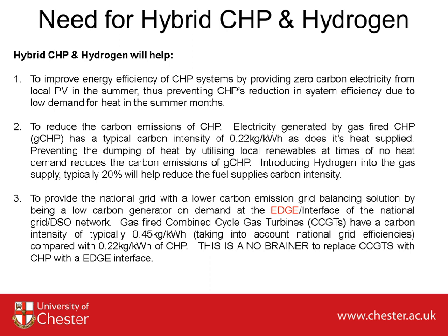It's generally considered that 20% hydrogen in the grid is likely to be at the acceptable level and not likely to get much greater than that. But if we can do more to generate hydrogen locally, then we could be able to change the Jenbacher engine, which started out being a diesel engine, is now a natural gas and LPG engine, and in the future it could be a 50% hydrogen engine, and let's hope so. And the CHPV system will start to move closer and closer to a net zero carbon distributed energy system.